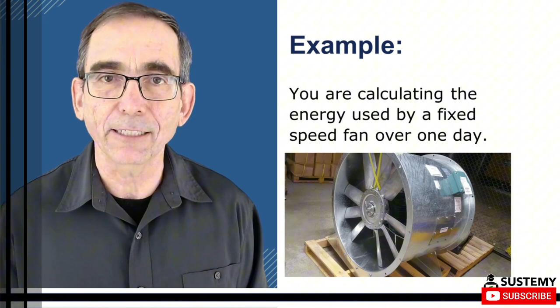You have the motor nameplate power, you write down the quantity of 10, and then you write down the units next to it, kilowatts. The estimated load factor, taking into account motor efficiency, that would be 0.7. That's dimensionless, or you could write 70%. The hours per day is 8 hours. The energy, which is the nameplate power times the load factor times the hours per day, is 56, and then we just multiply down those units on the right to get kilowatt hours per day.